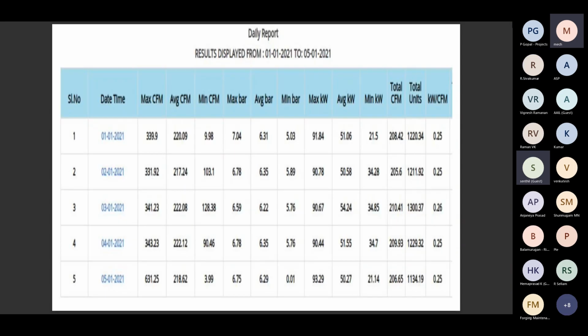Next one. So this is the output. See, 1, 2, 3, these are the various dates. What is the maximum CFM generated? What is the average CFM consumed? What is the maximum air pressure maintained? And what is the loss? How much loss is there in the pipeline? Everything is arrived at. Here the kilowatt per CFM is 0.25, next day 0.25, the third day 0.26. You can take these kinds of measurements: the maximum kilowatt consumed by the compressor, the average kilowatt, the minimum, the total CFM, the total units. Total units divided by total CFM gives the kilowatt per CFM. This way we can give the figures to the management on how the compressor is performing. This is the best system, by adopting IoT.